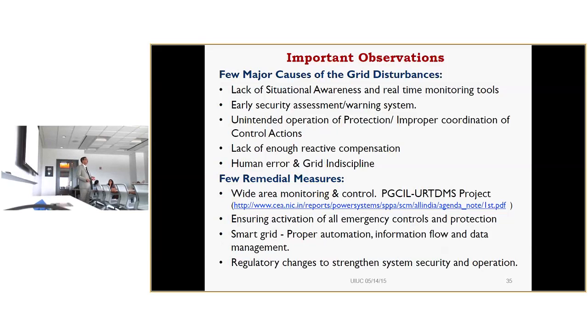In fact, they are going to have a dynamic security assessment tool which will be run periodically. And then the relay settings were not proper, so the committee recommended that you must go for an audit, a protection audit of all the relays. We have already done that. And we are also working on a supervisory protection so that unintended operation of zone 2 and zone 3 protection is avoided. Reactive power compensation was not enough, so we have gone for a lot of SVCs now. We have TCSC. We had only one SVC in the country, near our institute in Kanpur, a 400 kV SVC. Now we are going ahead with about 19 SVCs, and they have found the optimum locations.